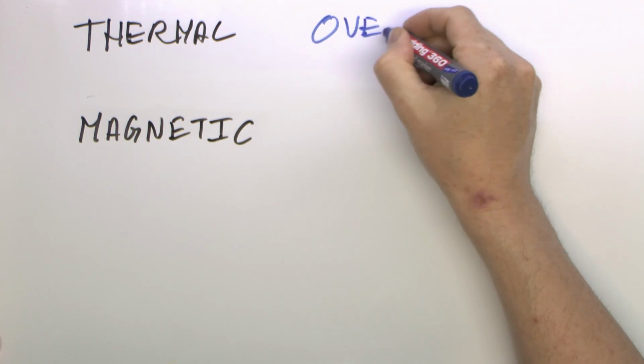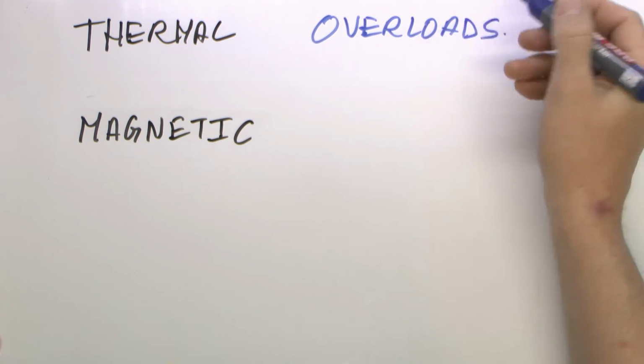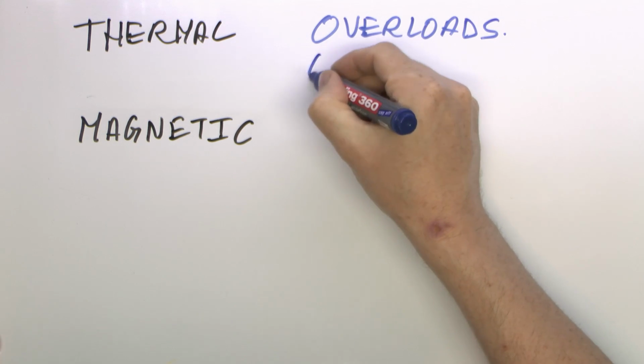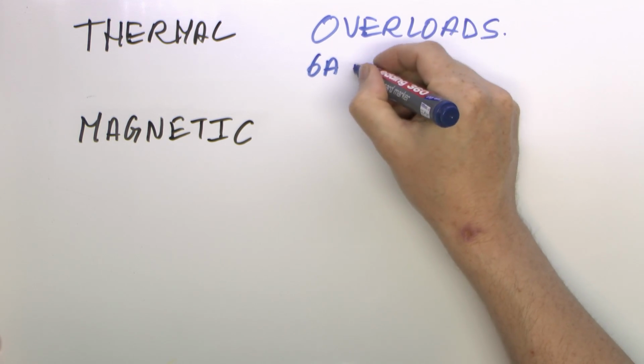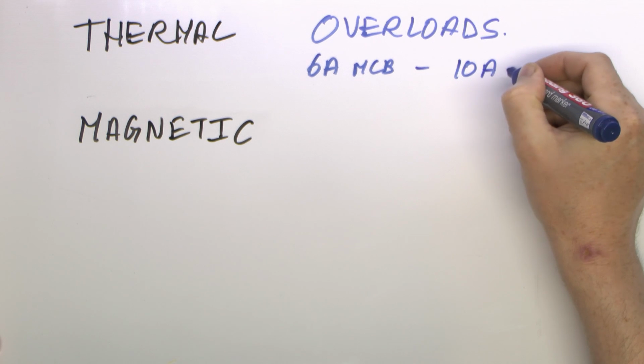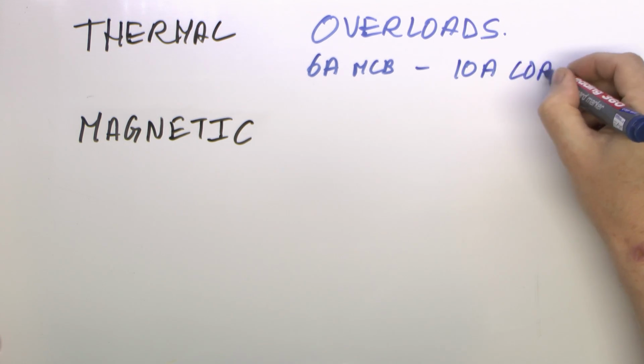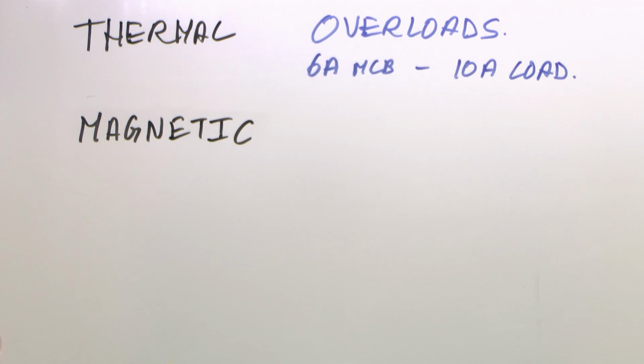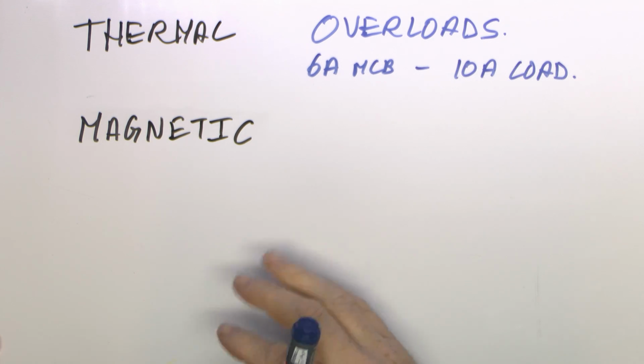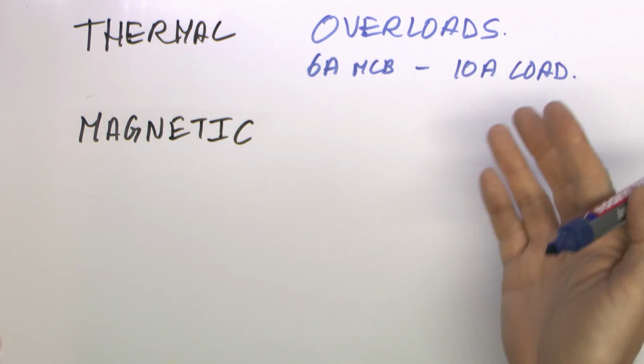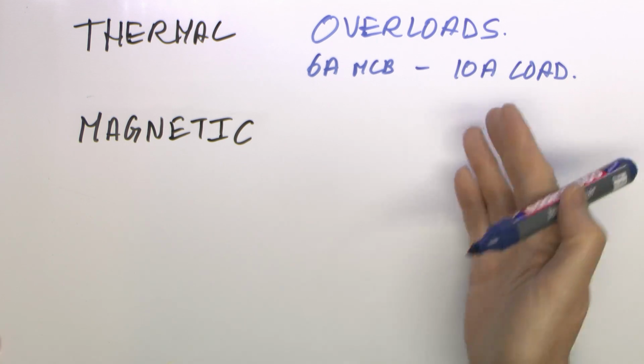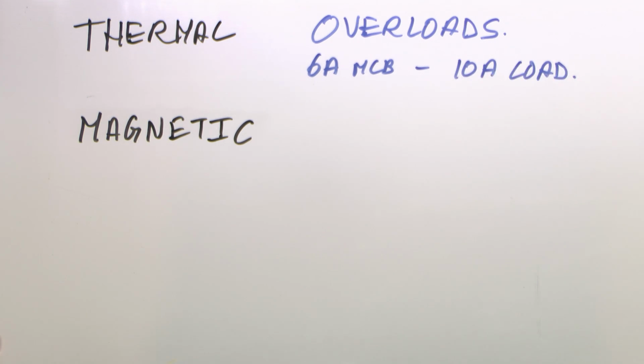So those are really just for overloads, and as an example, that might be the sort of thing if you had a 6 amp circuit breaker and connected a 10 amp load to it. That part of it is actually quite slow because it has to rely on the thing actually heating up, so that typically is going to take seconds, or in some cases even minutes, before the thing actually trips. But again, it's only for moderate overloads, so it does have current just flowing there, but it's just more than the rating of the device.